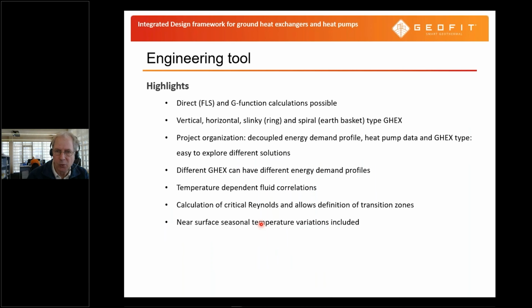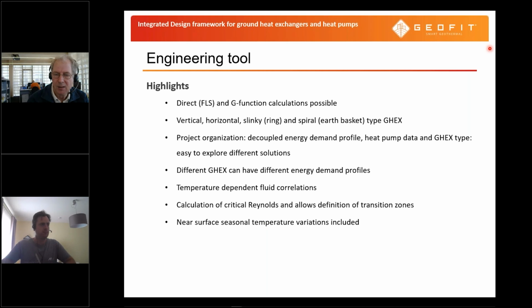I'm not going to talk too much about the engineering tool because it's just a lot of different screens and not very interesting. There are a lot of possibilities to edit the data, but some of the highlights are that we can do a direct calculation using the finite line source equations, but also do a G function calculation. The reason for this is in a different bullet because we can have ground heat exchangers, each with a different energy demand profile. So you can have neighboring systems with different energy demand.